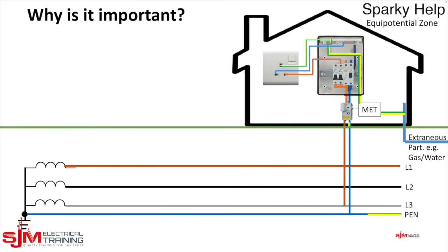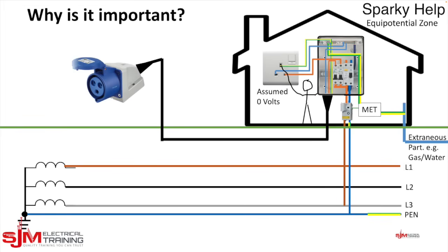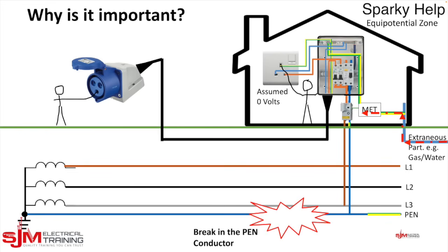So here we try it again, but this is an alternative that can happen. We touch this, it's not a problem, we create the equipotential zone, assumed to be 0 volts, and we put an outside supply in, and potentially nothing may happen because there is no difference in this case. But this time we get a break in the PEN conductor, and because there are other supplies further up, the return path now, because it can't go through the PEN conductor, will be through their extraneous conductive parts and through their earth, and could well now go through the CPC, because all it wants to do is go back to that star point of the transformer.